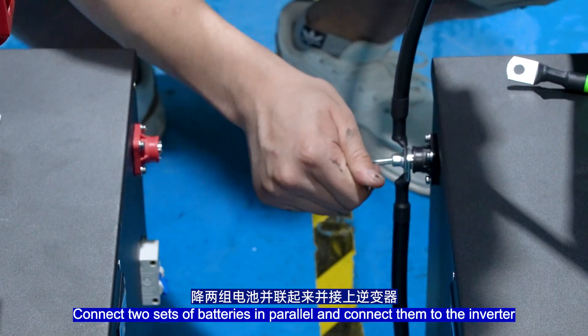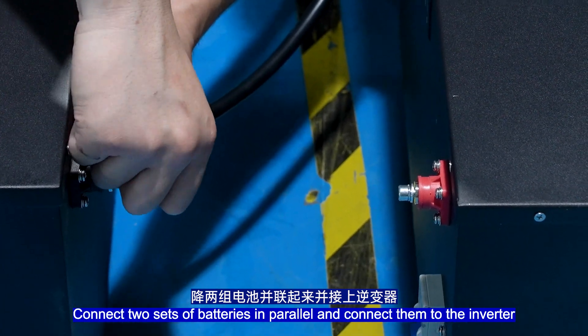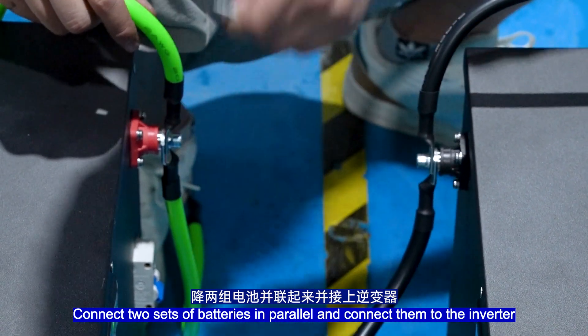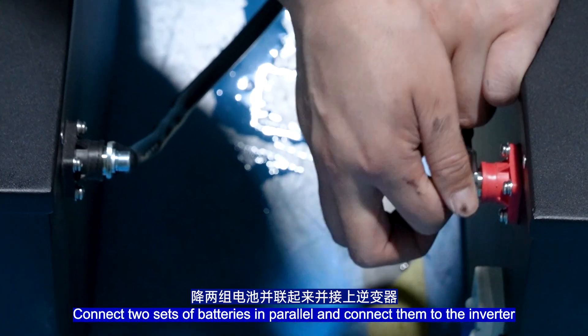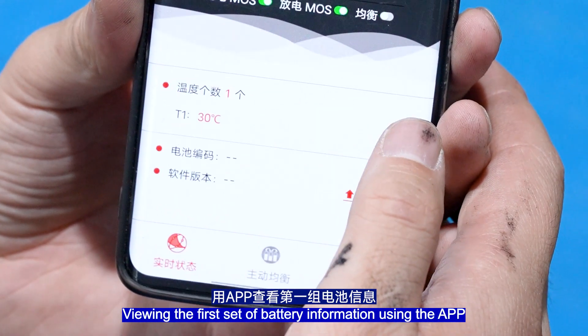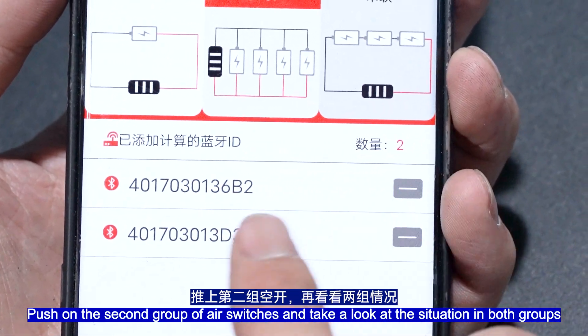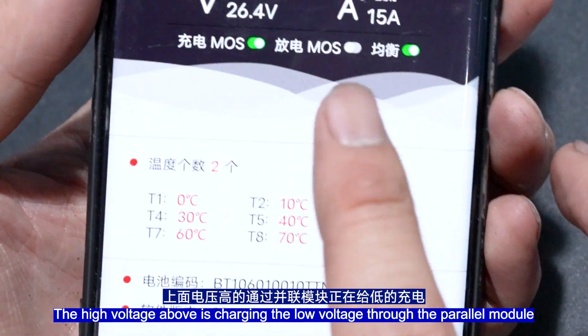Connect two sets of batteries in parallel and connect them to the inverter. Install the power pack. Viewing the first battery pack information using the app, the total voltage is 53.4V. The second pack voltage is 51.1V. Push on the second group of air switches and check both groups. The voltage of the second group is low and the charging mode has been turned off. The high-voltage pack is charging the low-voltage pack through the parallel module.